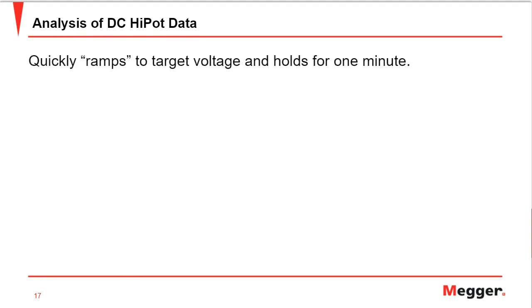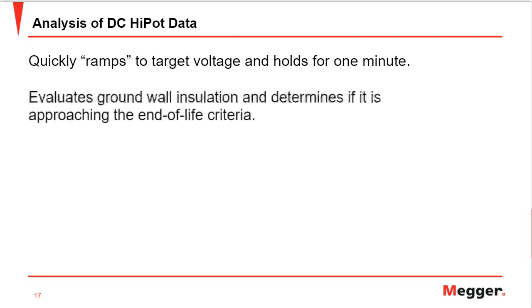Conventionally, a DC high-pot test ramps quickly to the target voltage, holds for a minute or less than a minute, and then measures the current. It's a very useful test to evaluate the ground wall insulation, and it also determines if it is approaching the end of life criteria, which again goes back to the insulation curve. It is also known as the ground wall stress test.